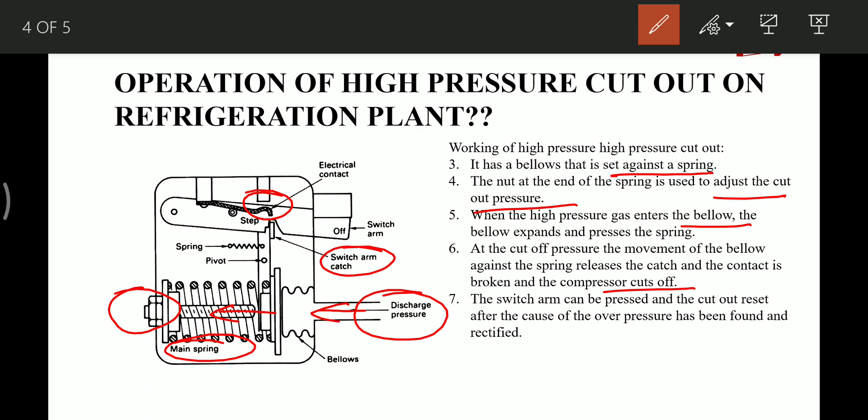The state of this high pressure cutout in this diagram is the activated state, that is why this contact is broken. For resetting, this switch arm has to be pressed in this direction and it will be reset, and this catch arm will be again set on these grooves.